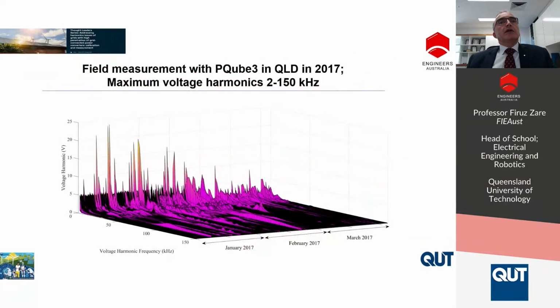So let's start with this slide, which is one of the measurements that I did in a residential area in Queensland. You see the harmonic frequency, or this is the maximum value. We have done lots of analysis. I just want to highlight that even the maximum value, depending on the measurement, shows that sometimes high frequency below 50 kilohertz can be significant. Having said that, this is one of the reasons we want to highlight that harmonics in the network at high frequency are very diverse and depend on how these devices interact together.